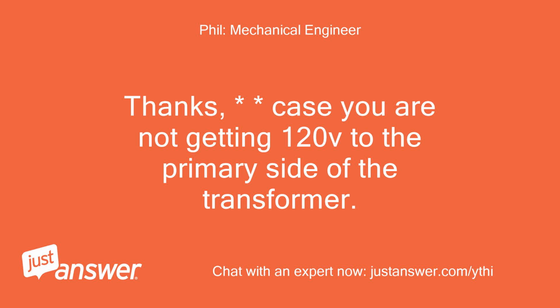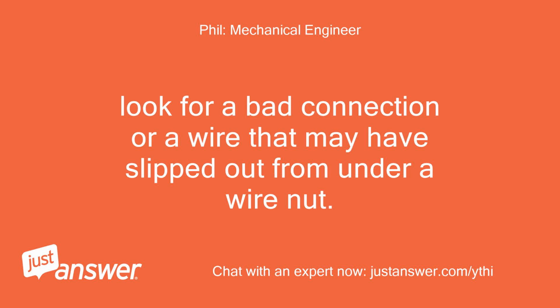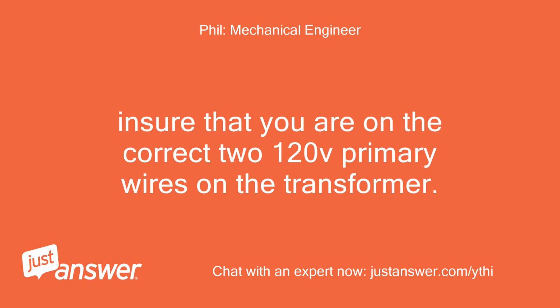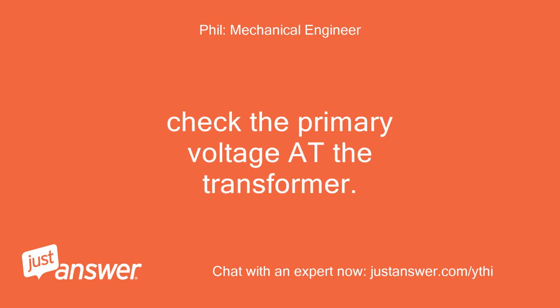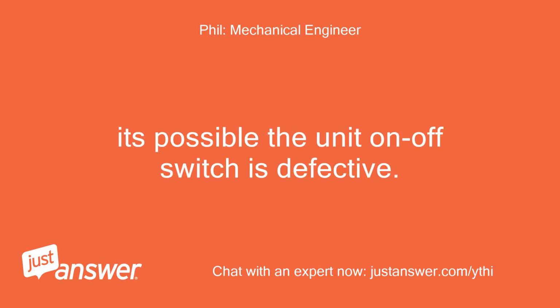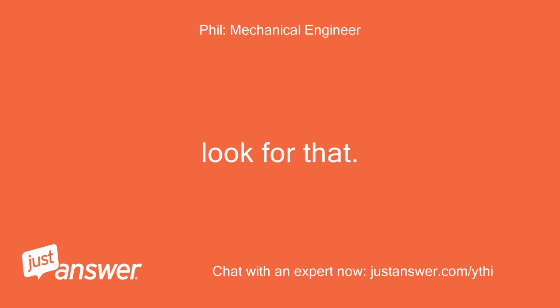Thanks. In case you are not getting 120V to the primary side of the transformer, look for a bad connection or a wire that may have slipped out from under a wire nut. Ensure that you are on the correct two 120V primary wires on the transformer. Check the primary voltage at the transformer. It's possible the unit on-off switch is defective. Look for that.